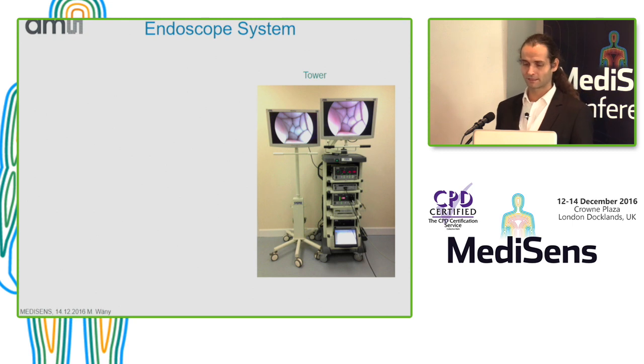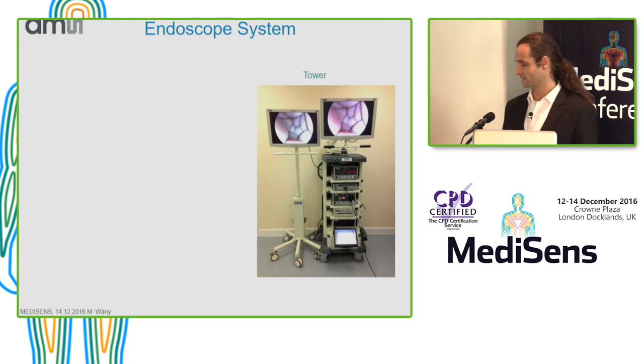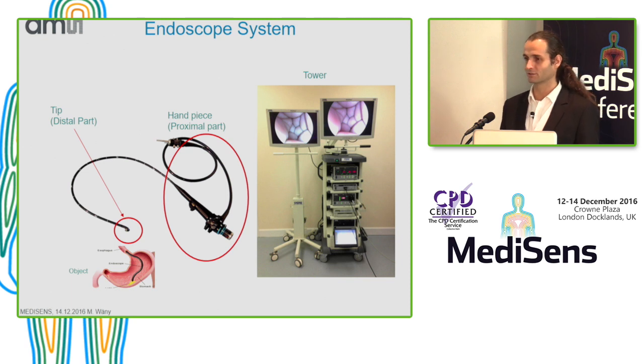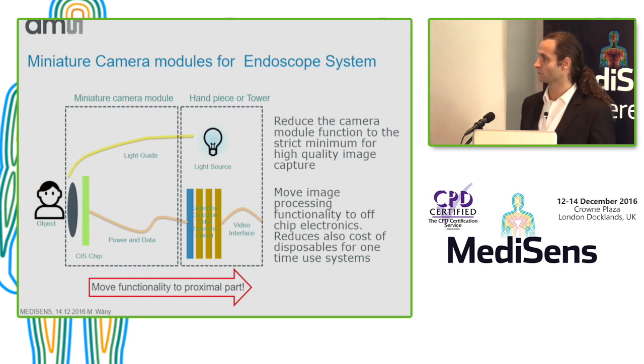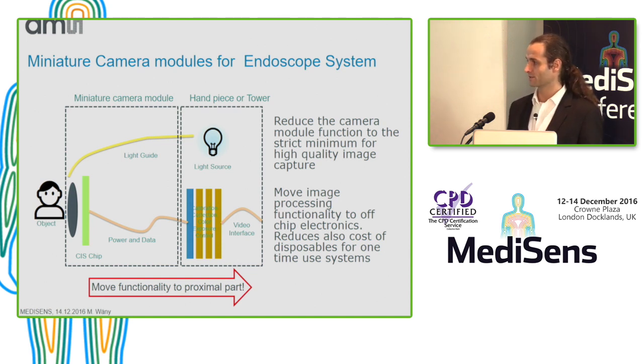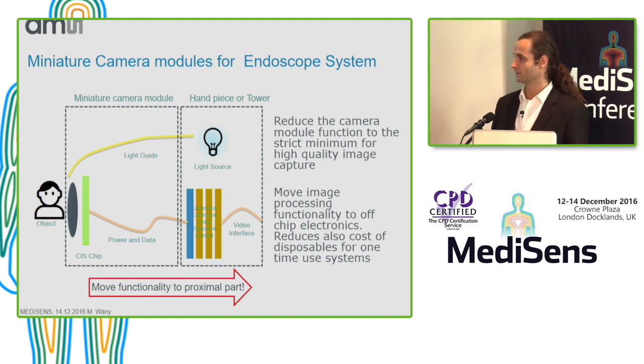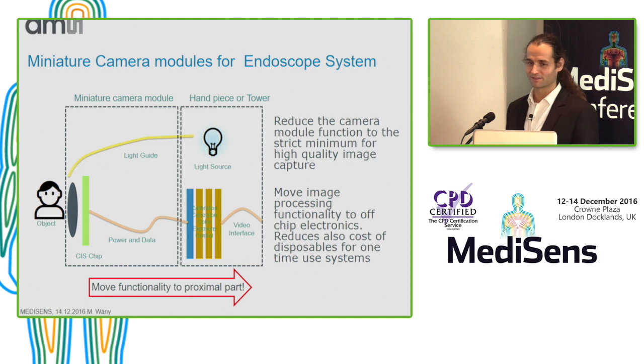If you look at an endoscope system, it basically has three parts: the tower, where the display resides; the handpiece; and the tip — the distal end, which is what you stick into the body. When making a miniature camera system, at the tip is where the size has to be small. One approach is to skip everything you can — move functionality to the handpiece or tower, to the proximal part where you have more space. For disposable parts, that also reduces cost, since you don't pay for things you throw away.